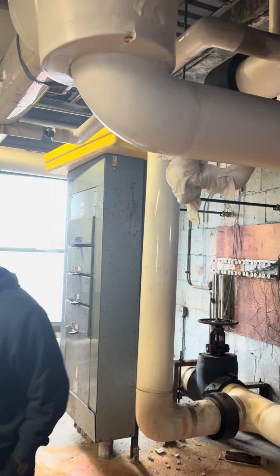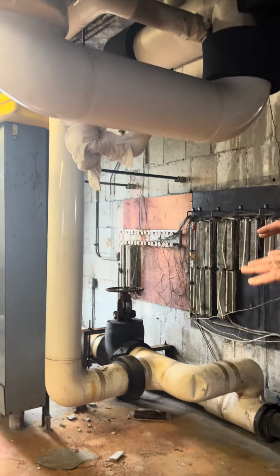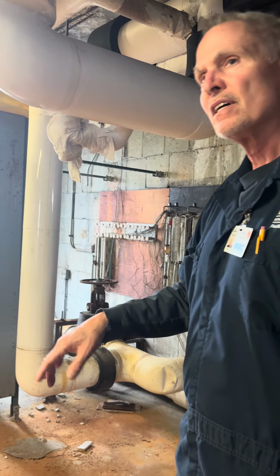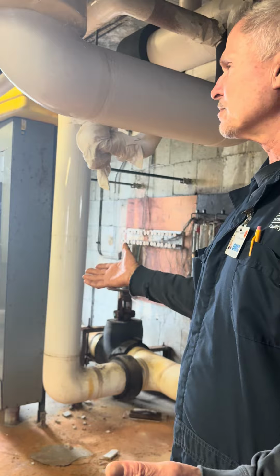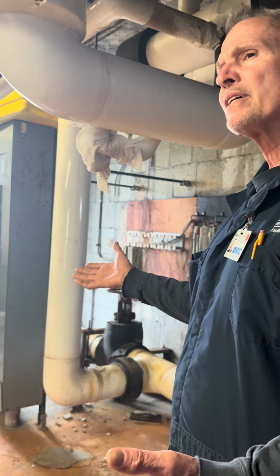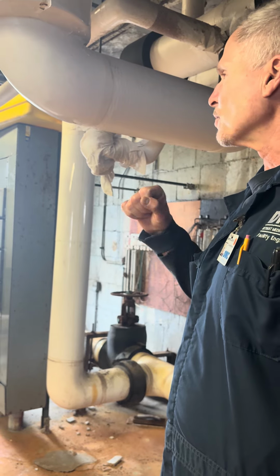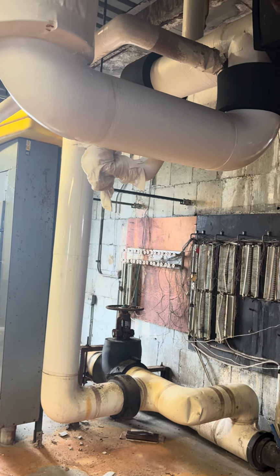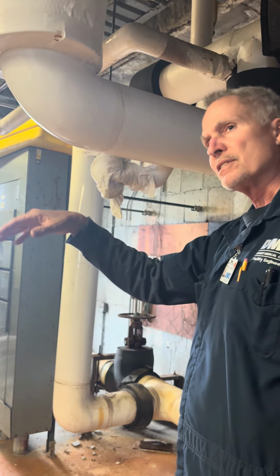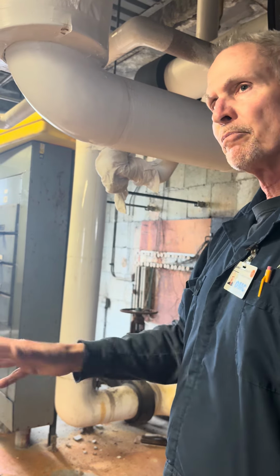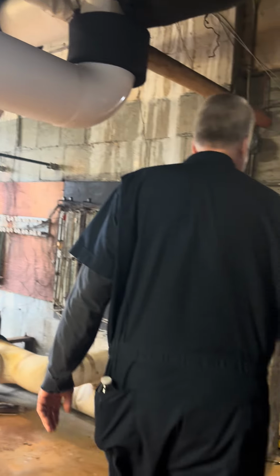Okay, so we come over here. This is a mixed system. So in other words, the convectors, like in his office, it's heat. In probably 3 weeks, 4 weeks, we're going to switch over when it gets warmer and stays warmer to cooling. So you open up the chill water system, and now you shut off downstairs in the basement. You have heat exchangers, bypass that, and run all the way through. You got to figure out this piping here. You got to open up those valves to keep going around.